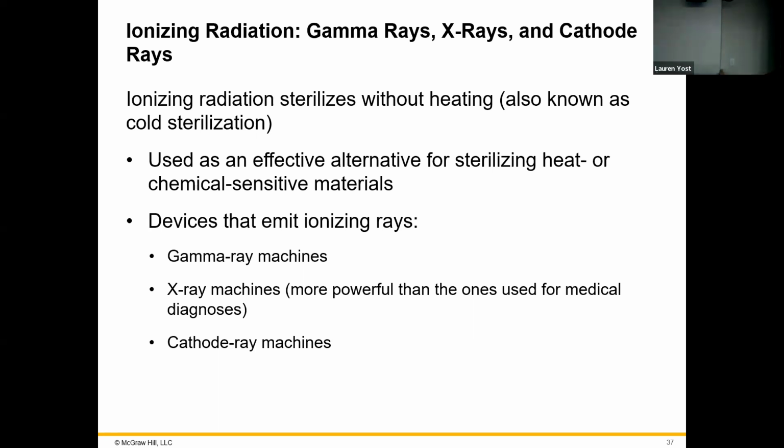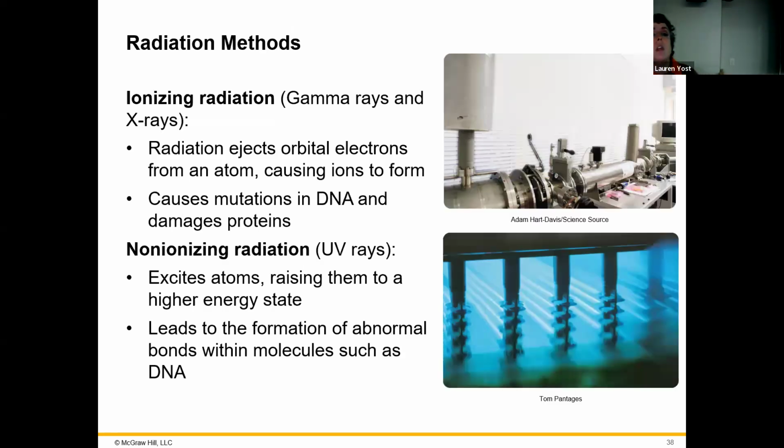So the whole thing is completely sterilized, all without having to treat it with the autoclave and risk melting the plastic or something like that. So you can actually have it sterilized in that package, and the whole thing is sterilized inside that package. So when you open it up, inside and out, completely sterile. So irradiation with ionizing radiation is actually really commonly used for our disposables. It's also commonly used for food products. So food products will often be sterilized with ionizing radiation. So pretty common for that.